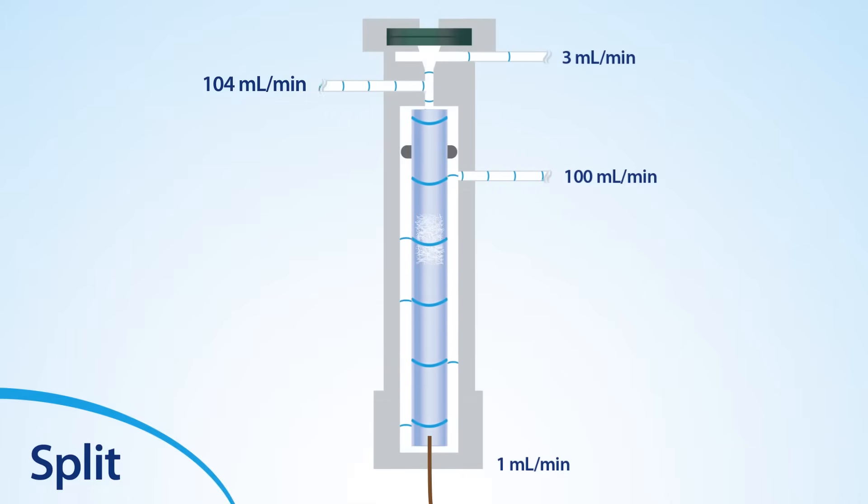This ratio, the split ratio, is determined by the user before starting the analysis. Split ratios typically vary between 5:1 to 500:1, with the higher the ratio, the lower the amount of sample that enters the column compared to what passes out the split vent.